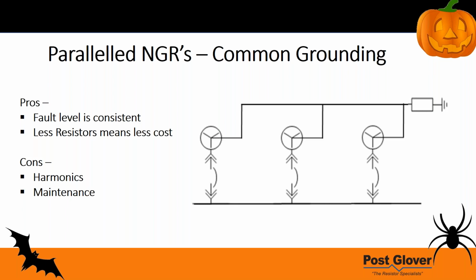You have parallel gens, so you have third harmonic contributions per gen—you're going to be dealing with third harmonics for this configuration for sure, so you have to worry about harmonics in this situation. The good news is, once again, you have one resistor. Let's say it's 400 amps—it's 400 amps no matter what you do, so it's a very consistent fault level.